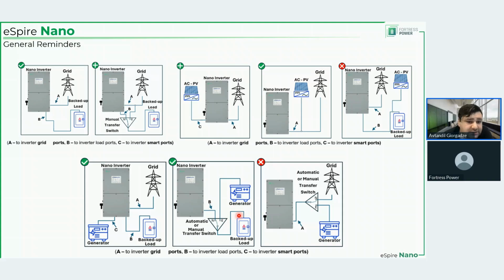So as long as the inverter is providing power, if this is an automatic transfer switch, then power flows through the bypass or automatic switch to the backup load. If the inverter stops outputting voltage and frequency, then the generator will start, the ATS will change its position, and the generator will feed the loads directly. This allows for the generator's autonomous operation, but what this doesn't allow for is having the generator charging the battery. It will only power the loads.